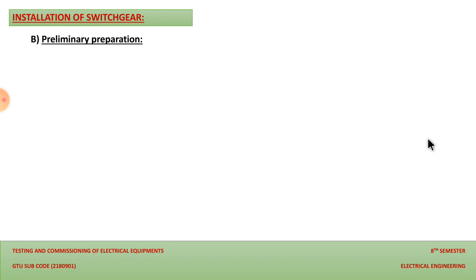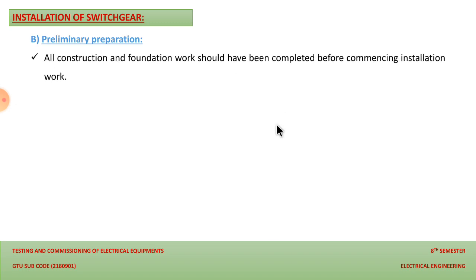And the next is, if we are installing our switchgear, the preliminary operation that we have to perform, that is, all construction and foundation work should have been completed before commencing the installation work. So it is necessary, because when we receive our switchgear at the premises, if we have not done certain preparation, then we need to install our switchgear at some other place, and afterward we have to take certain steps of protection. And if we have already done the preparation for the installation of the device, then we can directly put our device at our required place.